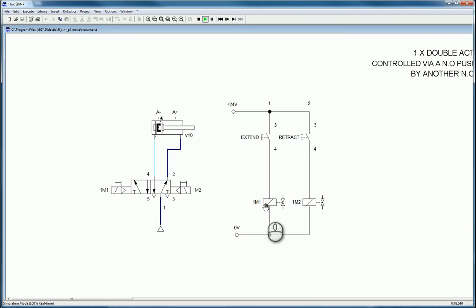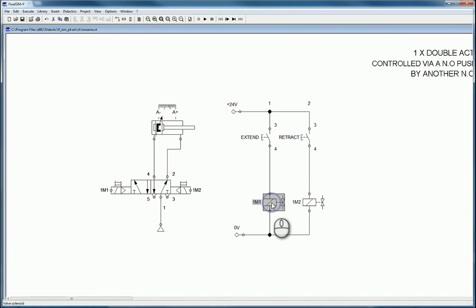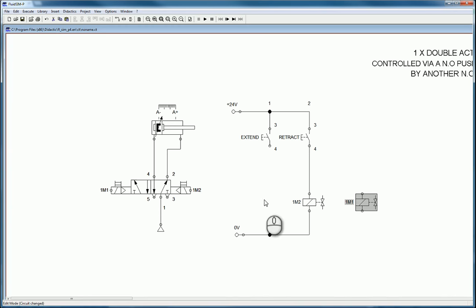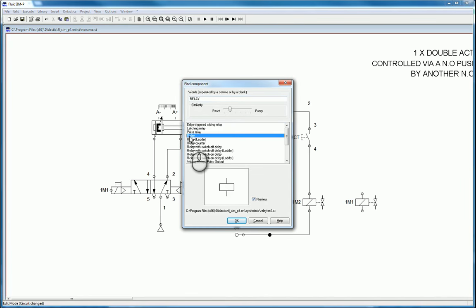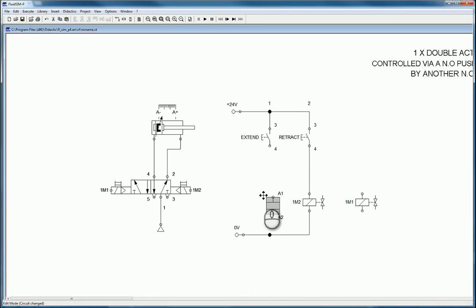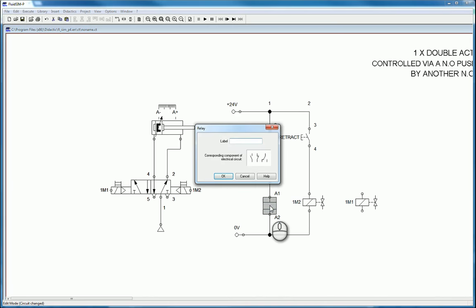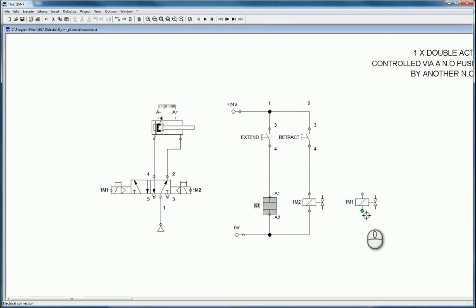Direct control means the push button is directly connected to the valve solenoid. Generally we don't want that — instead we want to indirectly control through a relay. Delete the lines currently connected and move the valve solenoid aside. Place a relay in where the valve solenoid was — this gives us indirect control. Label it K1 using the standard convention, then connect the valve solenoid back in.